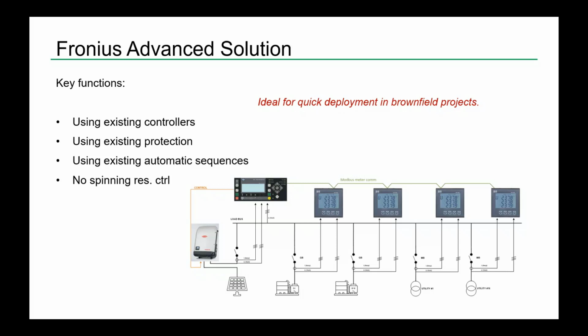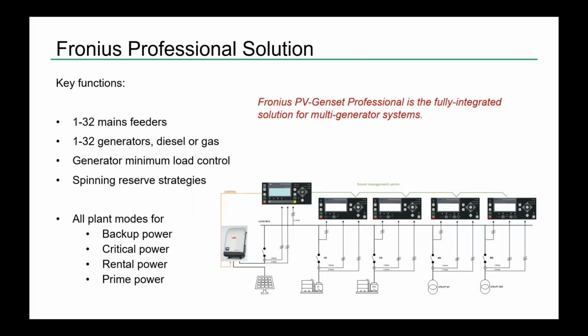It's a little bit different when you look at the professional solution. Here we have limitations as well. It's up to 32 mains feeders, 32 generators, or a combination of them, of course. So instead of 16, now you can make bigger plants. But it is a fully integrated solution for multi-generator systems. So you have the full backup, you have all plant modes available. This is for backup power, critical power, rental power, prime power. So this is the complete solution where everything is controlled by the DEIF.